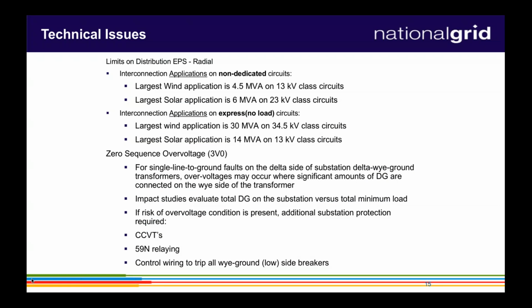In some cases, we do install dedicated feeders for renewables, and on a larger system that may be done on the 13 kV class, which is a majority of our system — the 15 kV class. We'll actually put upwards of 14 megawatts on a single dedicated feeder if the conditions are right. So a lot of penetration in our area.